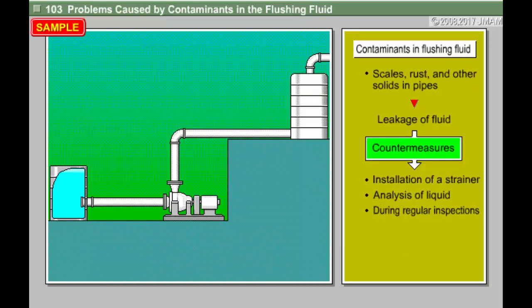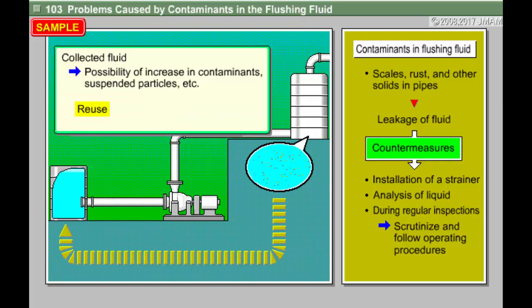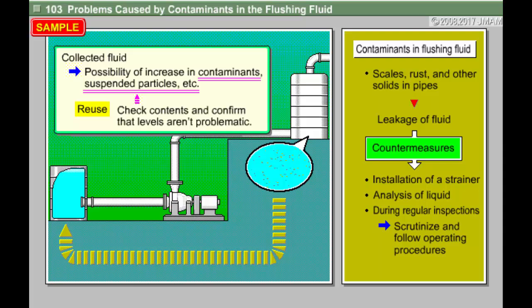Also, during regular inspections of the plant, we have to scrutinize operating procedures carefully and ensure that we follow them. In particular, when fluids are collected, for instance when equipment is shut down, there's a possibility of an increase in contaminants and suspended particles. When reusing fluids, we have to check their contents and confirm that the levels aren't problematic.